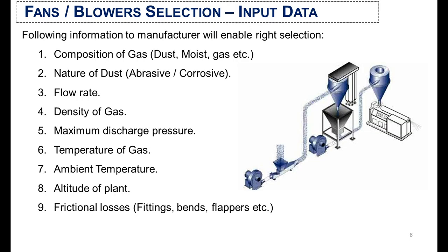The following information is required as input data for the selection of the right type of fan or blower. First, you need to know the composition of the gas being handled — whether it contains dust, moisture, or what type of gas it is, such as ammonia, simple air, or a combination of ammonia or nitrogen. Second is the nature of the dust — whether it is abrasive, corrosive, fertilizer dust, or simple solid material. Third is the flow rate of the gas.